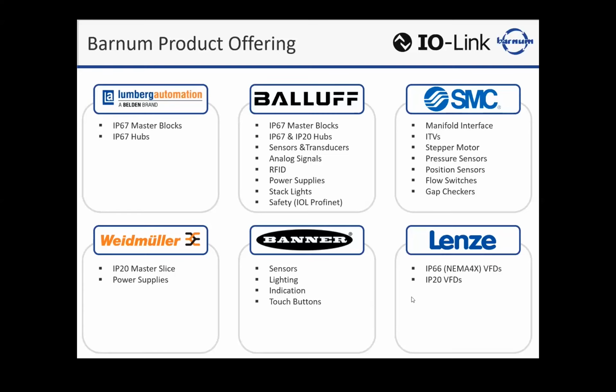So lastly, to touch on Lenze. Lenze is one of our lines for motion, for variable frequency drive servos as well. Explain what we have coming out here. So typically to this point, most people have either been using an IP66 enabled Ethernet or Profinet enabled drive in the field, or an IP20 VFD in the panel. Each has its pros and cons. The IP66 version, you obviously can do decentralized, but it's not very cost effective. It's a nice product, but very expensive.